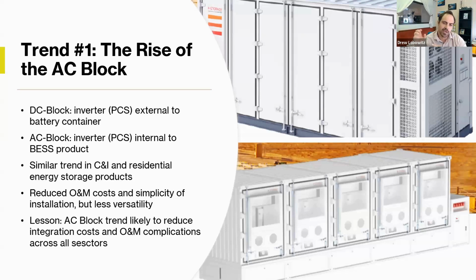On the top, it's the DC block, just the batteries. On the bottom, you can see it has an upper and lower portion—the lower portion is the inverters. So you have batteries on top, inverters on the bottom. The nice thing about this product is it puts out, I believe, anywhere from 480 to 600 volt AC power. You'd still typically hook that up to a medium voltage transformer and step it up to anywhere between say 20 and 40 kilovolts for distribution around the site.